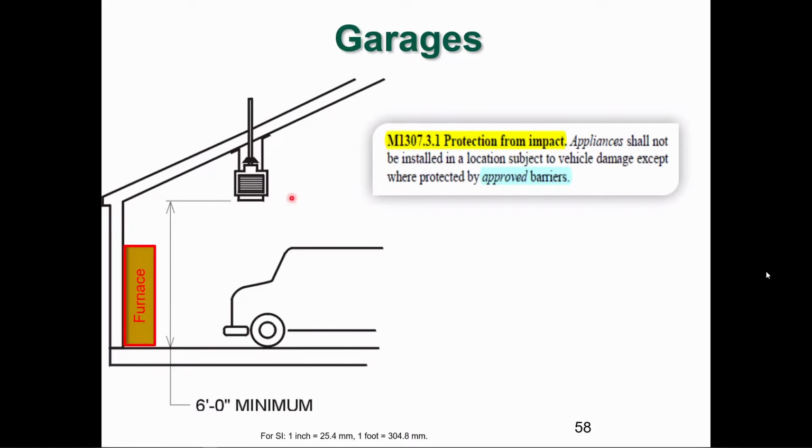Would you agree that this unit heater would be okay mounted up on the rafters or the trusses like that? The trusses and the rafters are designed to carry the load, there's no doubt about that. But wouldn't you agree that the vehicle could pass easily underneath this gas unit heater or oil-fired heater, right? Except the furnace is fair game, right? The furnace is fair game.